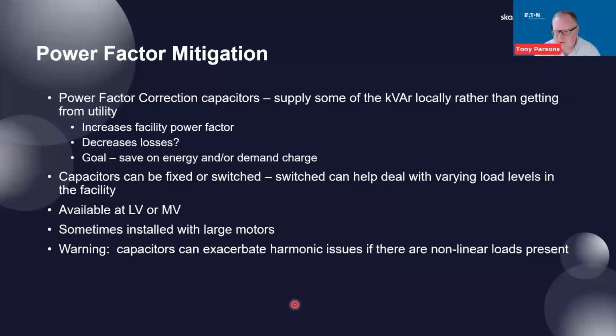As far as mitigation of power factor, like we hinted at on the last slide, the most common means of correcting your power factor is to apply capacitors in your system. The capacitors supply some of that reactive power locally rather than getting it from the utility. So you increase the power factor in the facility. Maybe you decrease the losses because we're drawing less current from the utility. The goal in any case would be to save on energy charges and/or demand charges from the utility. And in the best cases, the payback period can be pretty quick. You can talk about even less than a year in the best cases.